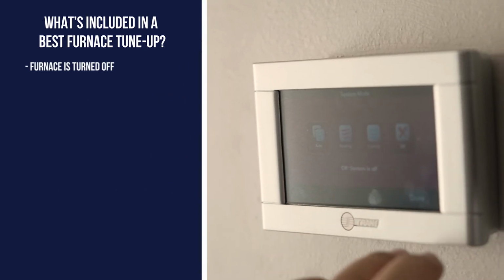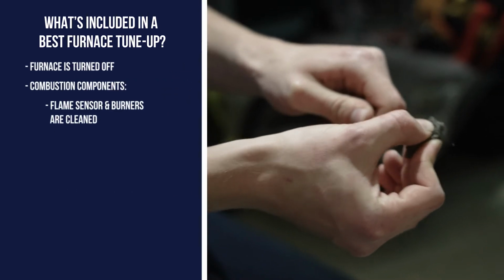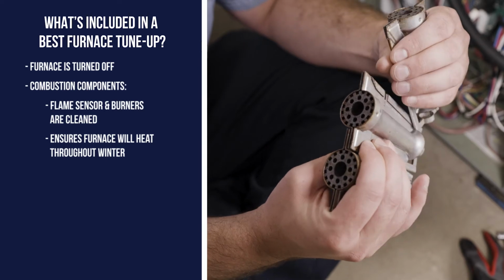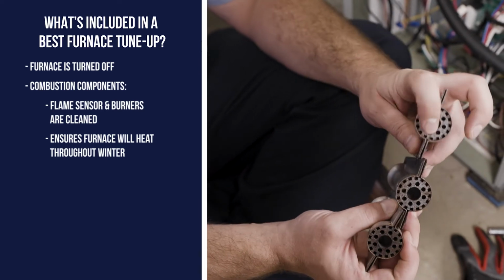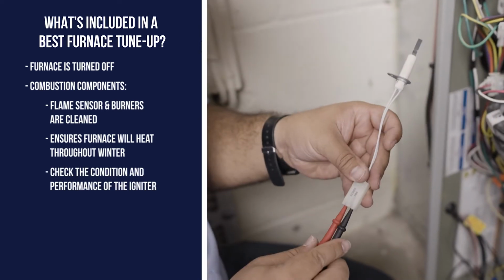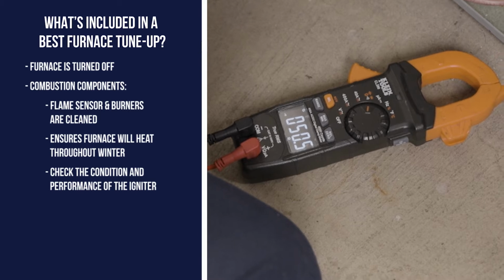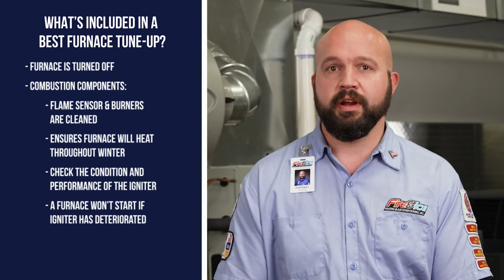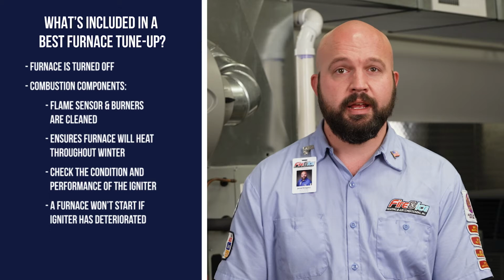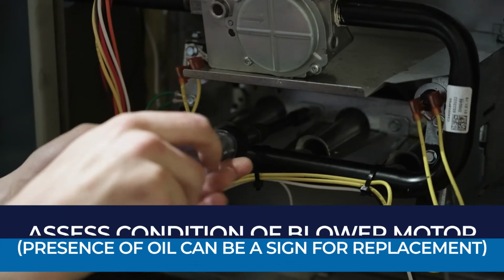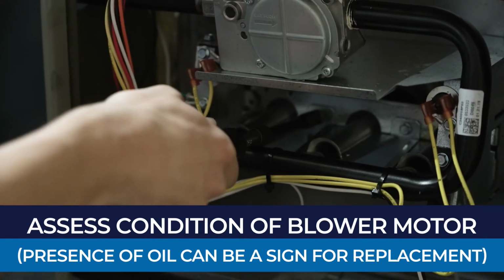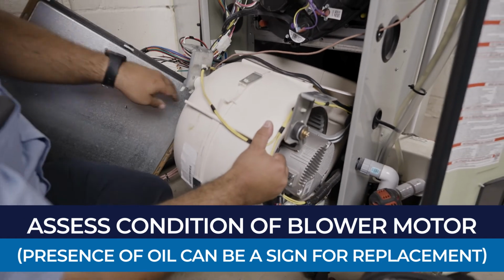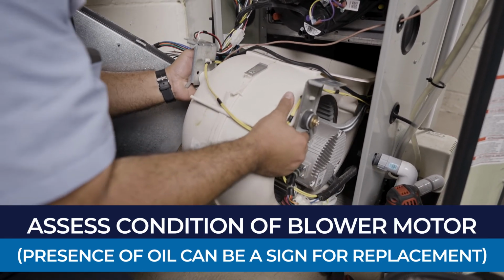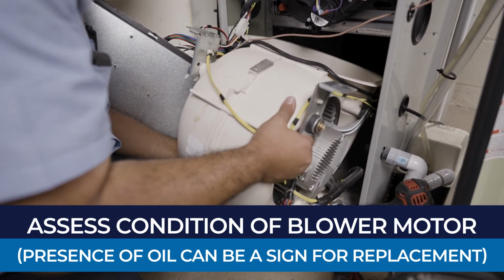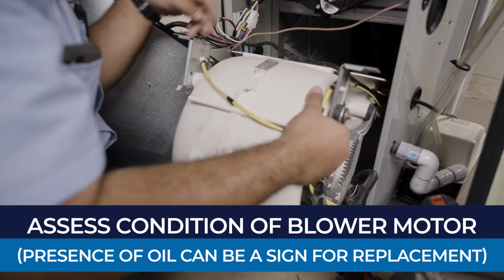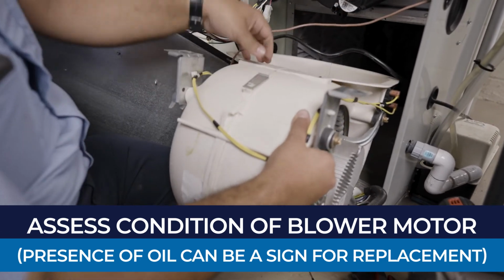Next, we'll turn off the furnace and begin cleaning the flame sensor and burners. Cleaning them is one of the best ways to ensure the furnace will continue to heat throughout the winter. We also check the condition and performance of the igniter. If an igniter has deteriorated too far, the furnace won't start and will need to be replaced. With the combustion components reassembled and wiring reattached, we turn our focus to the blower motor. With the best maintenance plan, we will pull the blower out and assess its condition for any signs of oil. The presence of oil could be a sign that the motor needs replaced.